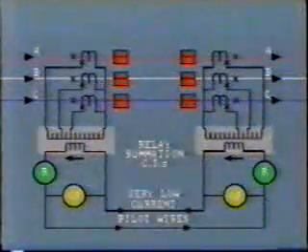In order to check pilot protection, we need to take in-service readings at each end of the line by measuring the value of secondary current flowing in the operating coils and restraint coils. With a phase comparison scheme like this, we would expect to find 0 or very low current flowing in the relays and pilot wires. This would indicate that the CTs are correctly balanced.